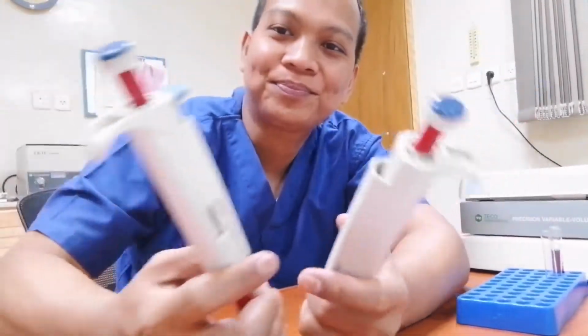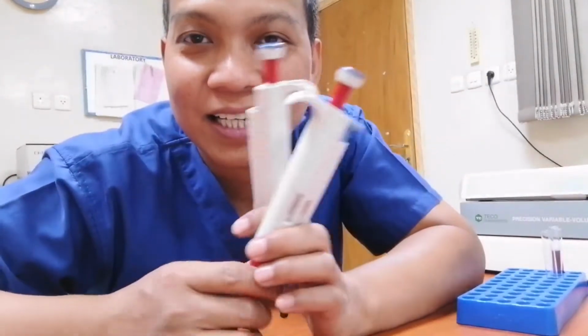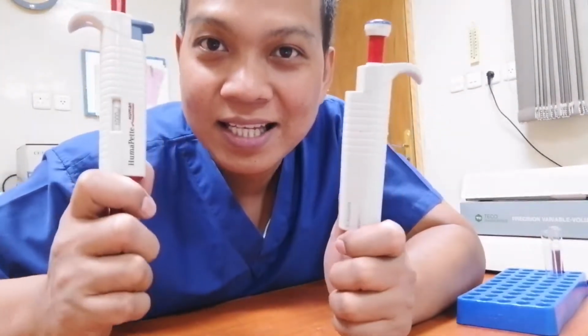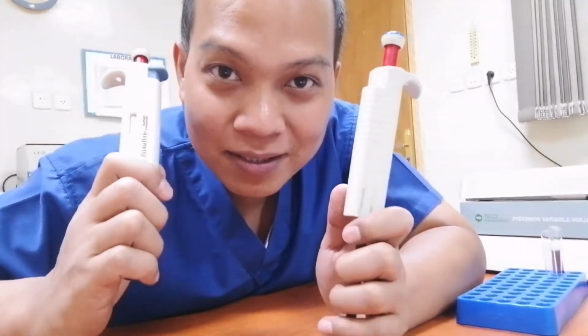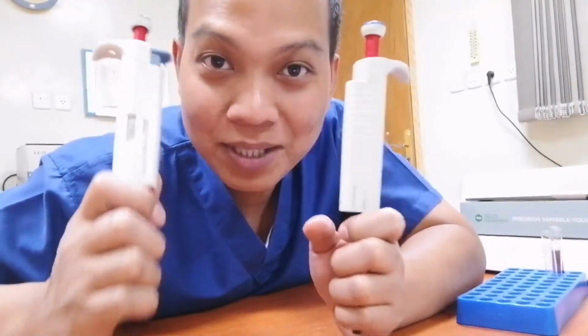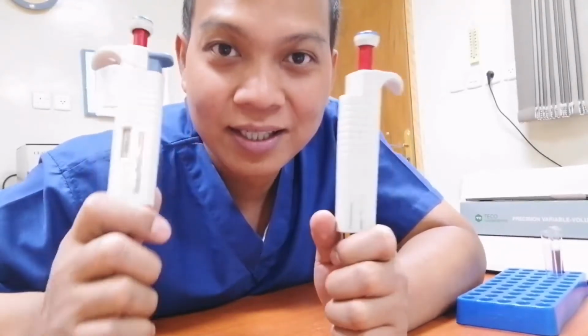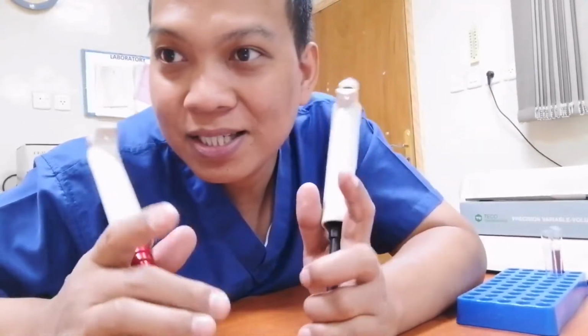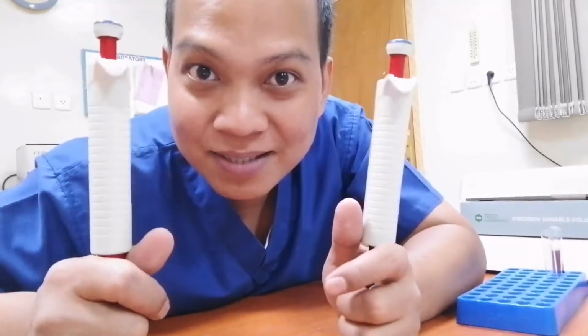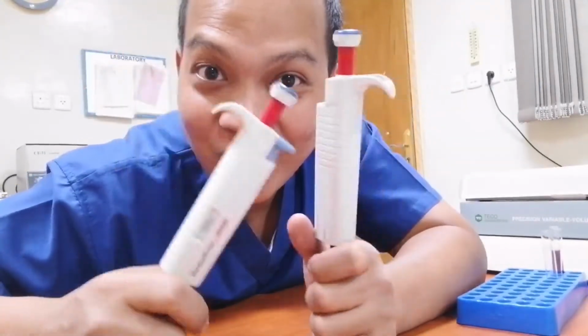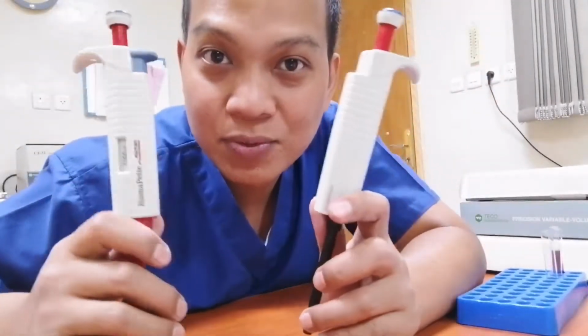So we will see. Based on the clinical laboratory standards, these pipettes must be checked and calibrated every 3 months to 6 months. Okay, every 3 months is better, because any discrepancies in volumes dispensed by this pipette may affect the result. Did you hear me? So we will check this one, okay?